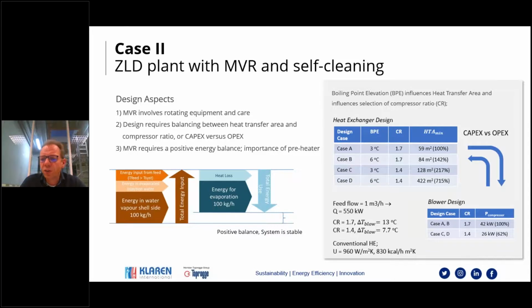To give you an example, if the compression ratio is 1.4, then this blower for this typical case would require 26 kilowatt. But if you increase the compression ratio to 1.7, it becomes 42 kilowatt. So if you put 42 as 100%, then the compression ratio of 1.4 is almost 40% lower. So really important. But this has another side of the coin.